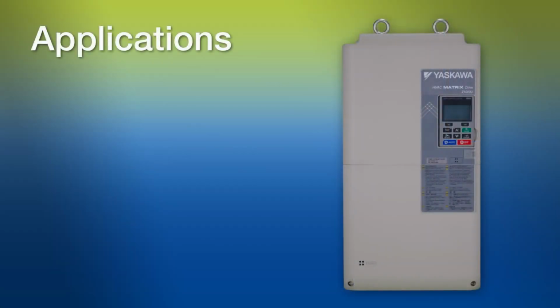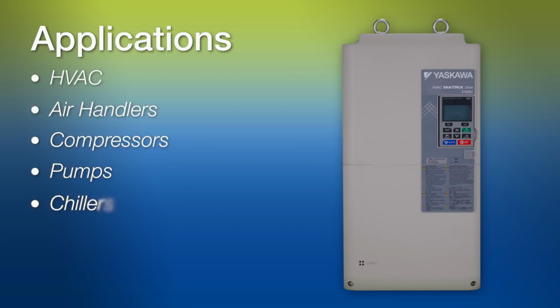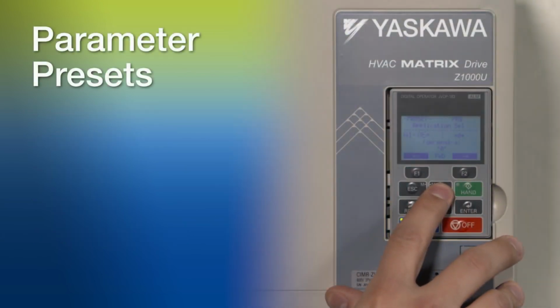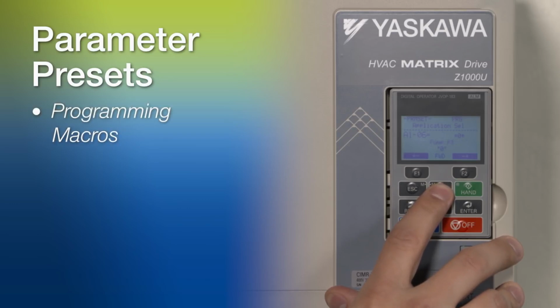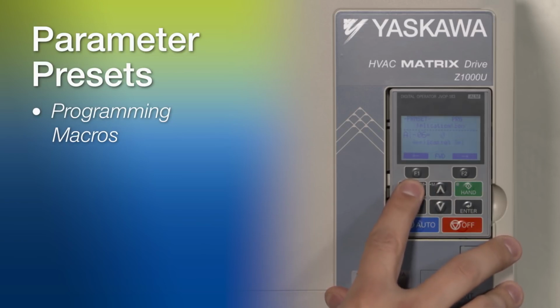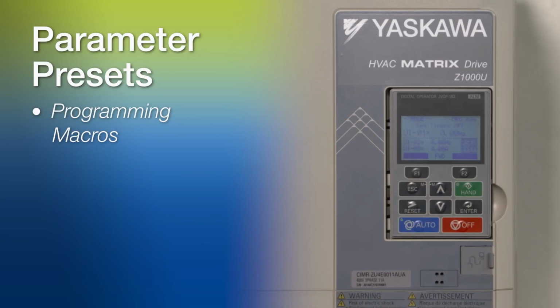Consistent throughout the Z1000U ratings is the fact that input amps of the Z1000U also match the NEC ratings, which will assure installers that input and output wiring gauges will be consistent. Applications include HVAC, air handlers, compressors, pumps, chillers, and cooling towers. And since the Z1000U is specifically designed for HVAC applications, there are a number of parameter presets that can be used to make startup faster and easier to meet specific application needs. These programming macros are all organized logically into groups. Select special functions from a multitude of possibilities to perfectly match your machine's requirements.